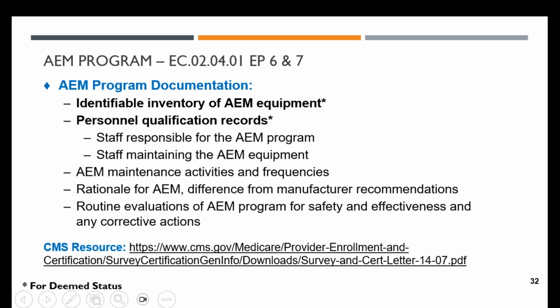Can we say it for the end? You can have both at the same time. Yes, you can have certain equipment on an AEM, and then certain equipment, like imaging equipment, you're not going to put on an AEM. That would violate a Joint Commission standard. But maybe you're choosing to put your infusion pump on an AEM because you have history that it doesn't reduce patient safety and you haven't had any corrective issues with a specific model. You're going to do that consideration in AEM management. But we'll have a whole discussion at the end. So for more info, you can look at this link. It's also in our PowerPoint.